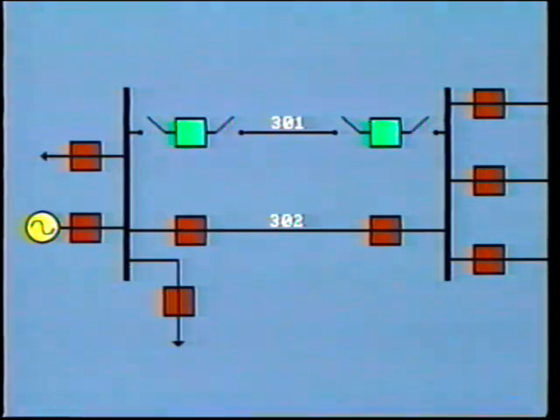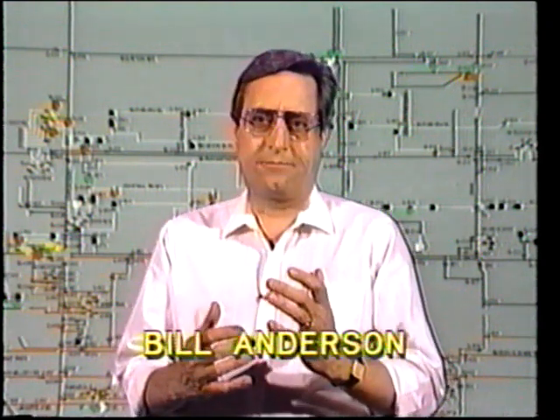But hold on now. What's happening here? Look, the bus protection has operated and cleared the bus, including the generator. Disaster, an outage, and interruption to customers. So what caused this inadvertent trip? Well, something has obviously become crisscrossed at some point. Perhaps the technician, by mistake, is working on the wrong circuit.